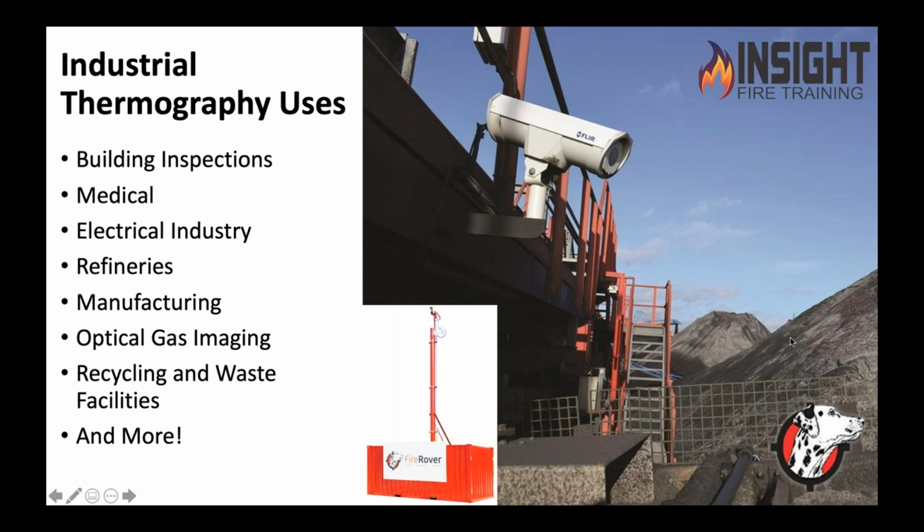There are other thermal imaging cameras, like Ryan said, it's not just plug and play. There's numerous types of cameras, but there are ones that are specifically tailored for gases. Remember this, most thermal imaging cameras measure surface temperatures, not gas temperatures. If you want one that measures gases, you're looking at optical gas imaging. It's a whole different level of cameras.